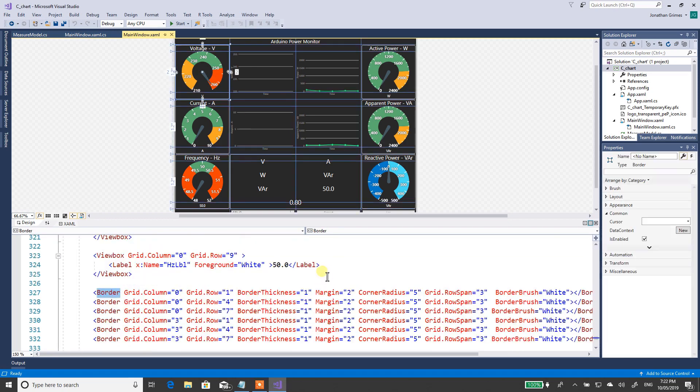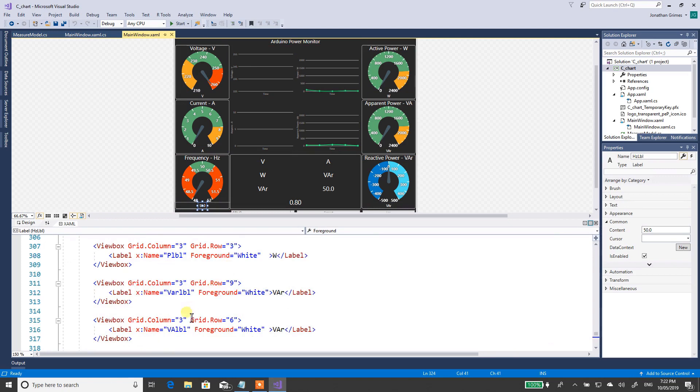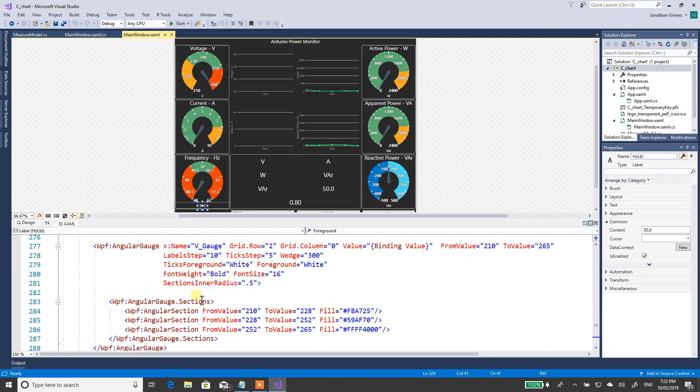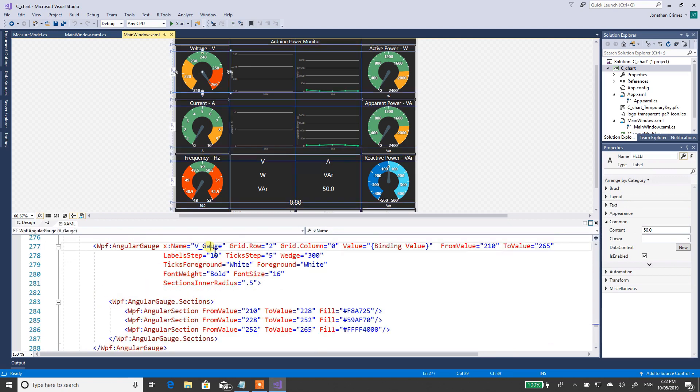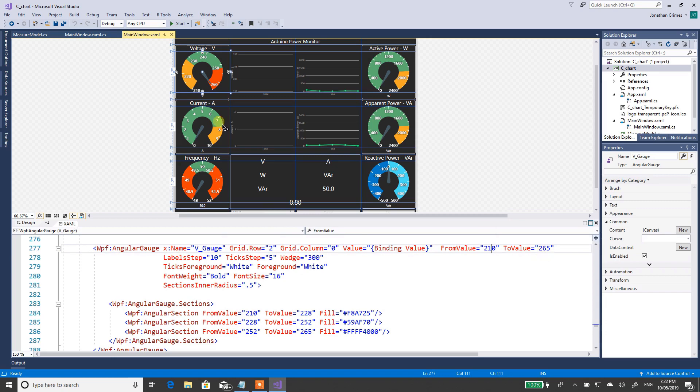I'll just show you how to change the quantities on the gauges. I'll just find one of the gauges down here. There's a frequency label, scrolling up. So this is the voltage gauge, the V gauge. You can see the name is V gauge. Now you can see how it's got from 210 to 265. Then you can change down here. You can change from 210 to 228, I've got that colour. 228 to 252, I've got that colour and so on.